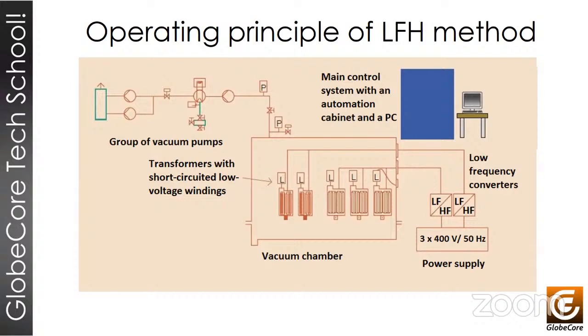During the process, the high and low voltage transformer windings are heated to a typical drying temperature of 110 to 120 degrees Celsius, as in the solvent vapor drying process. In order to monitor the drying process, and especially the winding temperature, special monitoring methods should be used to prevent the formation of overheated areas and, as a result, damage to the insulation.